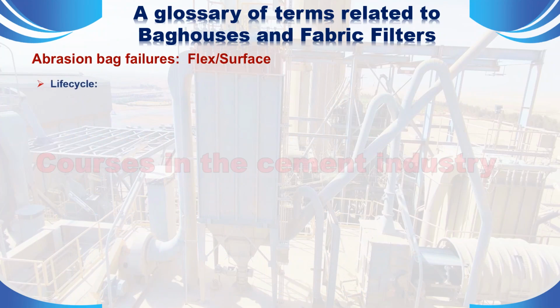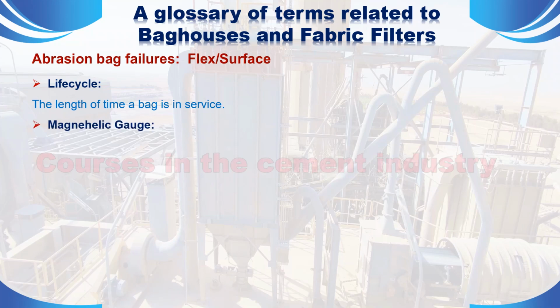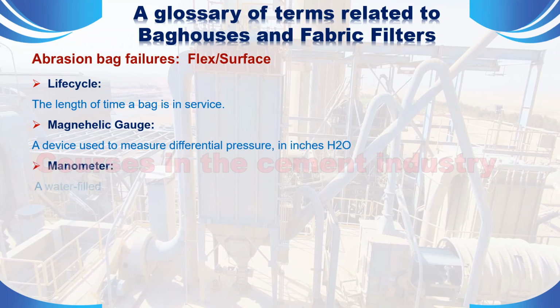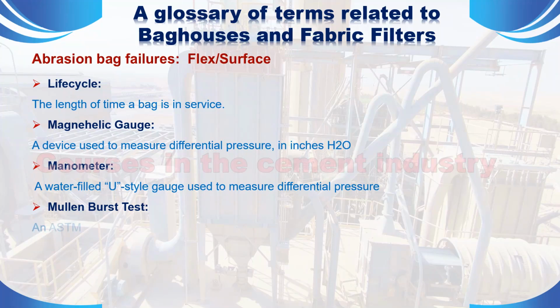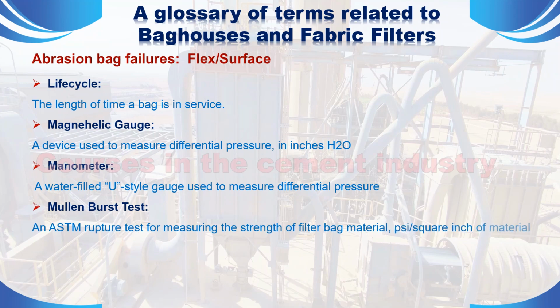23. Life cycle. The length of time a bag is in service. 24. Magnehelic gauge. A device used to measure differential pressure in inches H2O. 25. Manometer. A water-filled, U-style gauge, used to measure differential pressure. 26. Mullen burst test. An ASTM rupture test, for measuring the strength of filter bag material, PSI per square inch of material.